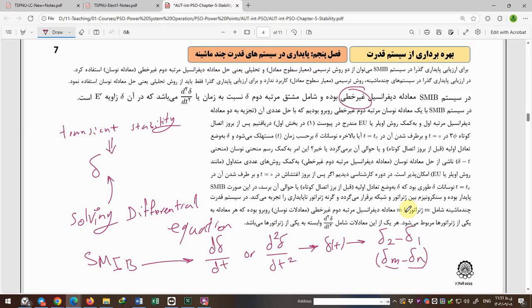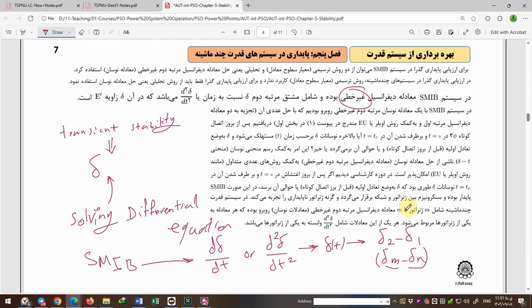If this difference between two deltas of two generators is limited, or its oscillation is limited, this means we have stability between the two synchronous generators. If this difference between the two angles gradually increases or decreases, this means we have instability in the power system.